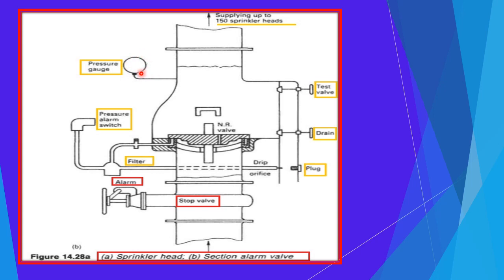This is the pressure gauge installation. This is the pressure alarm switch which is fitted over here. This is the filter arrangement, and here the test valve arrangement, and the drain valve and plug. So this is the complete arrangement of the sprinkler head non-return valve. What happens once the sprinkler starts operating is that the water starts flowing to this side, and you can see this is pressurizing, and this non-return valve is lifted up.